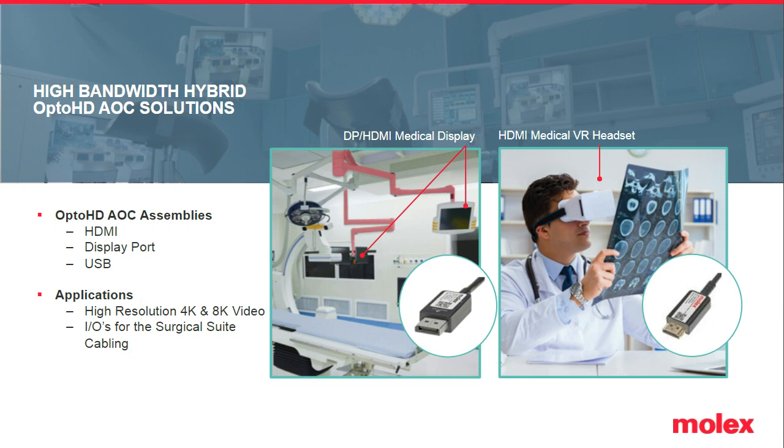Compared to traditional all-electrical cables, the hybrid optical cables are thinner and flexible, allowing them to be easily installed and fit in crowded medical equipment. The hybrid Opto HD AOC technology uses a patented optical engine to convert the electrical signal to optical at the opposite end of the cable. The result is a galvanic isolated signal with improved speed and longer bandwidth transmission distances within a thin cable that is flexible and lightweight.